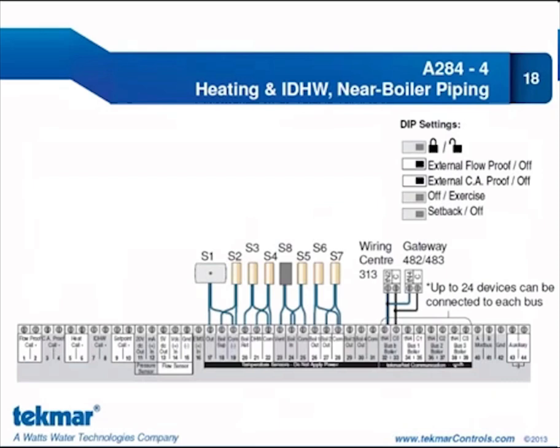Now, because we have these four buses and we can connect up to 24 devices on each bus, that means we can have up to 96 devices. So it really allows us for a large commercial type system. One thing to note, however, is it is only boiler bus. We cannot accommodate any mixed buses on the 284. They are all boiler bus.